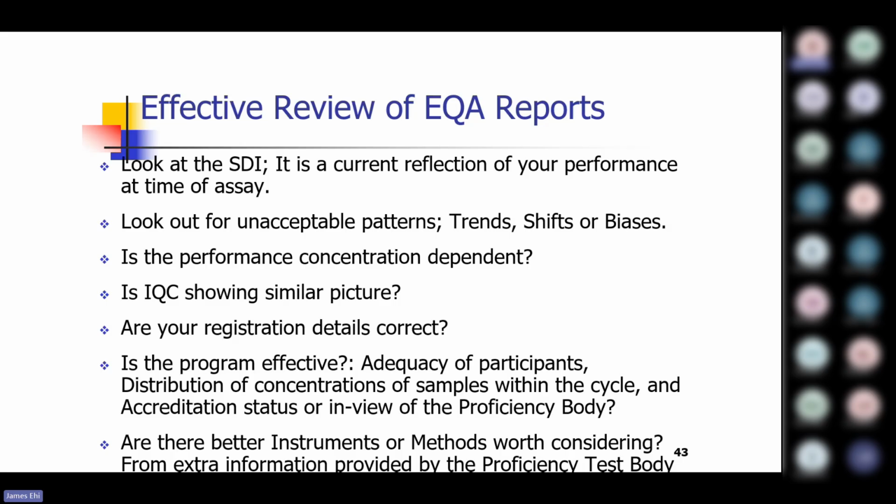So when you are at that high limit or that low limit, whether you like it or not, at those ranges in your calibration curve, your result will not be precise. And sometimes accuracy will be impeded. That's why some people will say, I've recalibrated it severally. It's not improving because it's within the upper region of the measuring range of your analyzer.